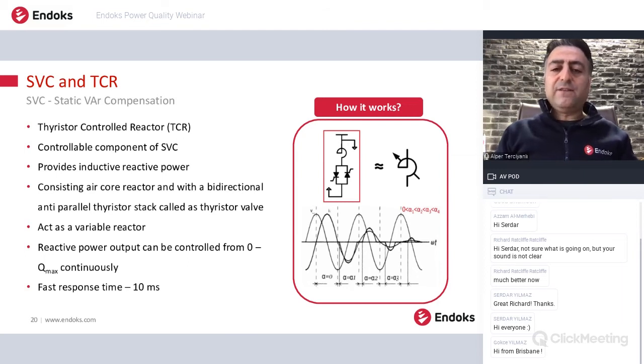So the thyristor valve is acting here as a valve actually. We can adjust the reactive power flow from the reactor itself with an electronic system, and we can control the reactive power from 0 to maximum in a continuous way. And the response time of the thyristor is 10 milliseconds. But of course, the total or overall system response time is a couple of 100 milliseconds because we have a controller and a PI controller in the system. The PI controller is working in feedback. We have a closed loop control, and we have a PI control on that. So the total response time of the system is a couple of 100 milliseconds, actually around 5 to 6 cycles in a typical case.